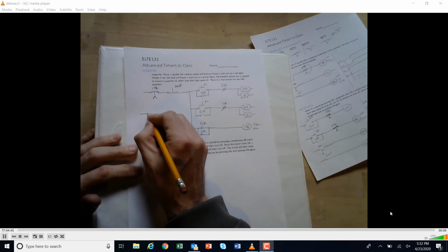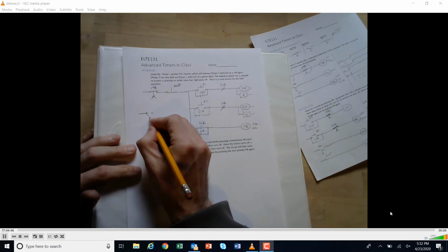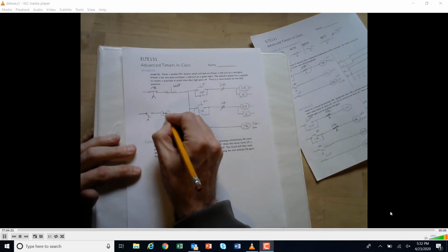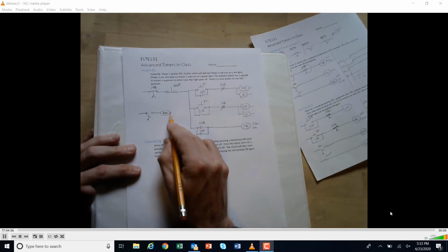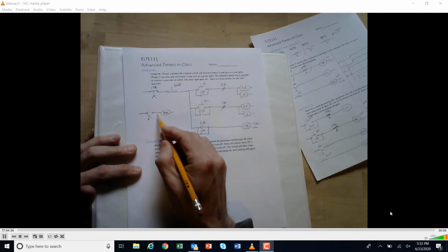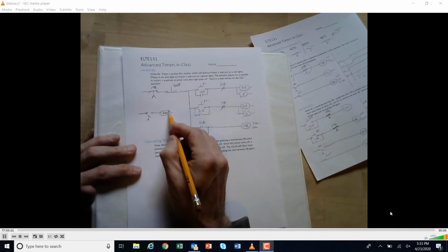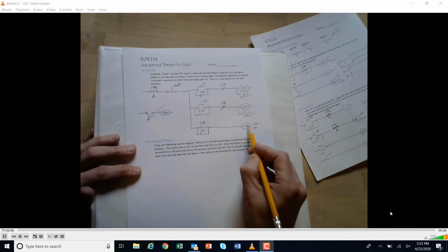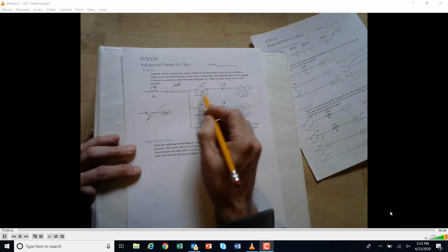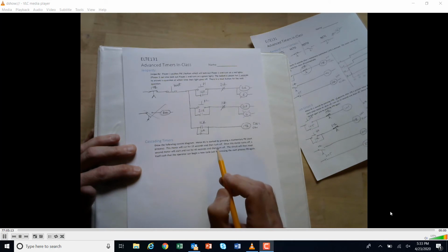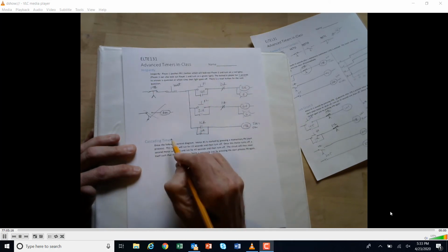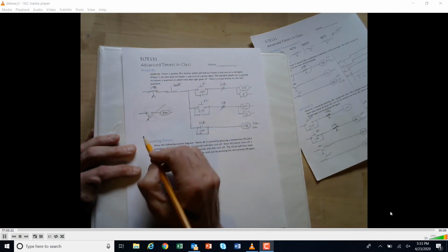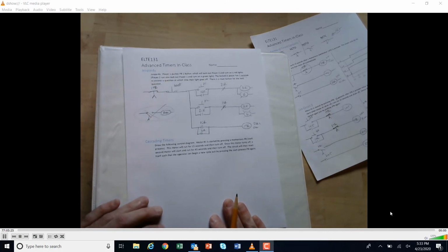And that was the other thing that I was saying. We could have had another run here, which would have been a normally open time closed, and that could have went to a buzzer, right? So that this buzzed, right? And then we'd have to do something to hold this on, to have another timer, to have it buzz for a while, because as soon as this times out, this opens, resetting everything, including the timer that opened this up, and then it would shut again. So the buzzer would need another timer before it reset everything. It's a little more complicated, but I'm sure we could figure it out.